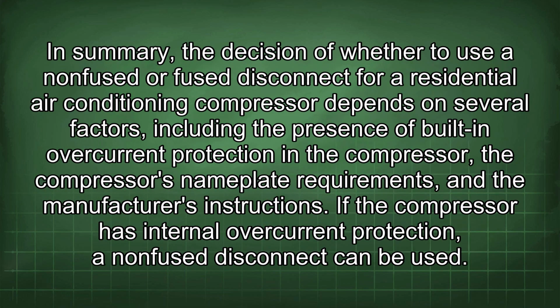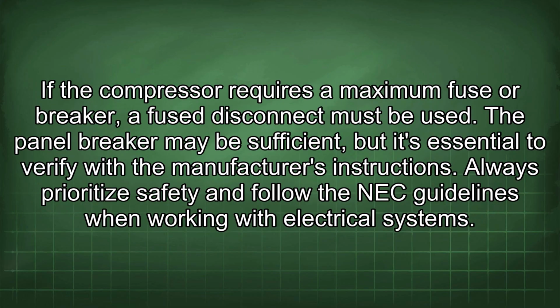In summary, the decision of whether to use a non-fused or fused disconnect for a residential air conditioning compressor depends on several factors, including the presence of built-in overcurrent protection in a compressor, the compressor's nameplate requirements, and the manufacturer's instructions. If the compressor has internal overcurrent protection, a non-fused disconnect can be used. If the compressor requires a maximum fuse or breaker, a fused disconnect must be used. The panel breaker may be sufficient, but it's essential to verify with the manufacturer's instructions.